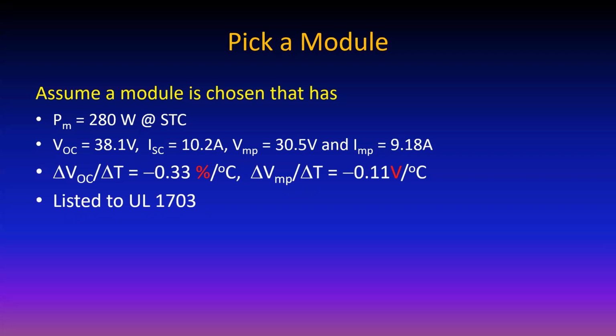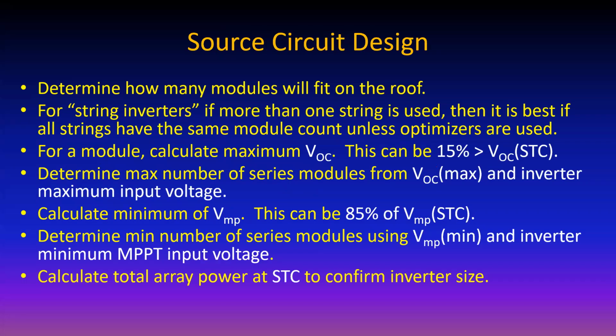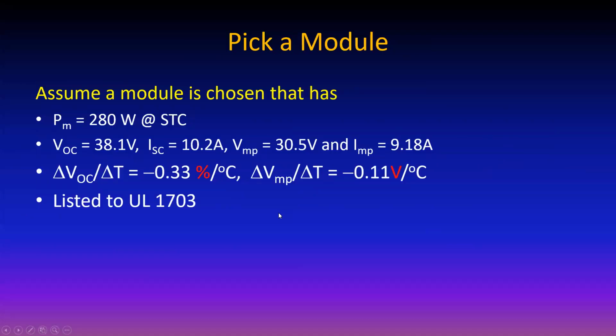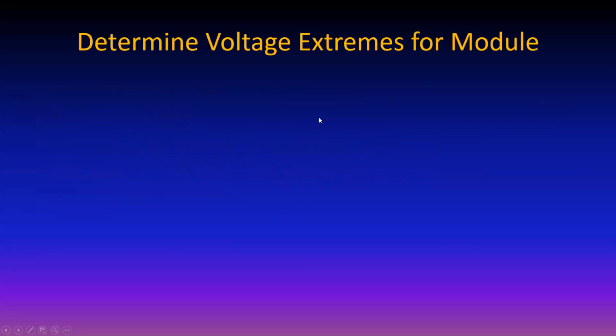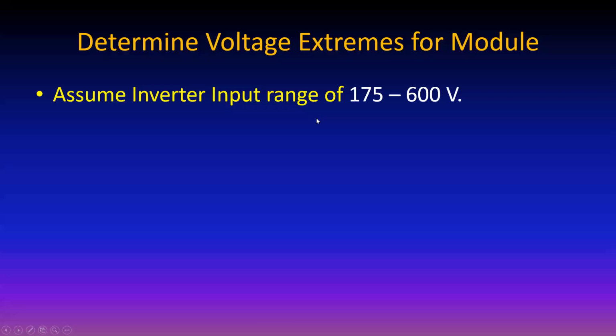They just iterate: they measure the power, then they move the voltage a little bit, measure the power again, and decide whether to move the voltage up or down. This is all done with the DC to DC conversion devices, and they've been at it for a long time, and they've really got it down to an accurate science. Let's back up here. Okay, and again, the module is listed to UL 1703. These are the numbers that apply to the module. So now let's put it in and calculate what the voltage extremes are.